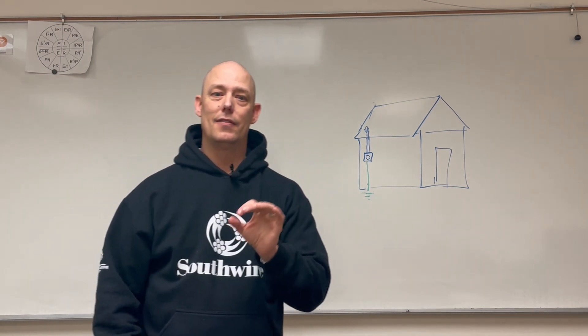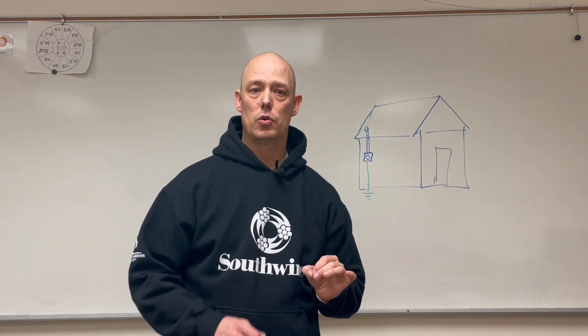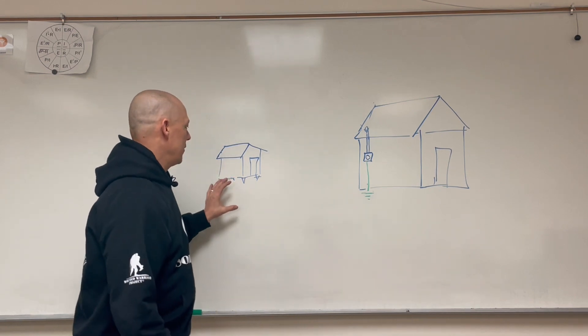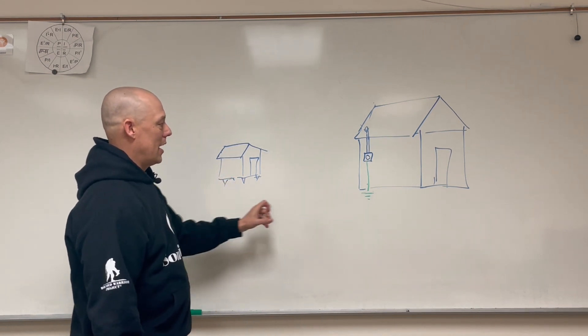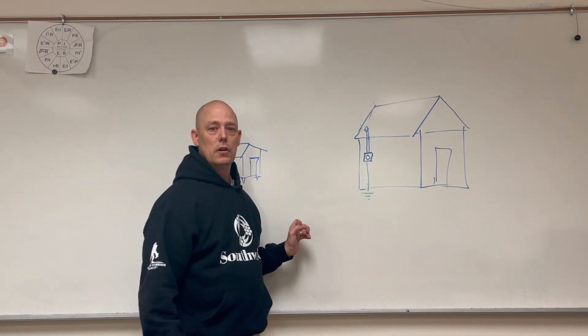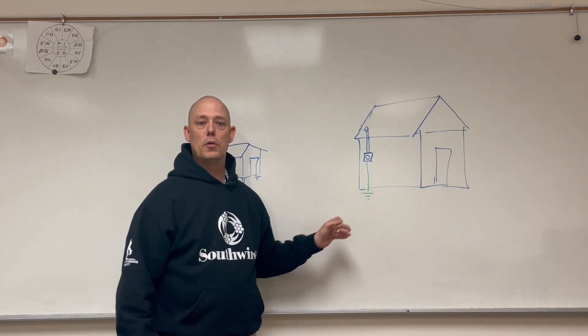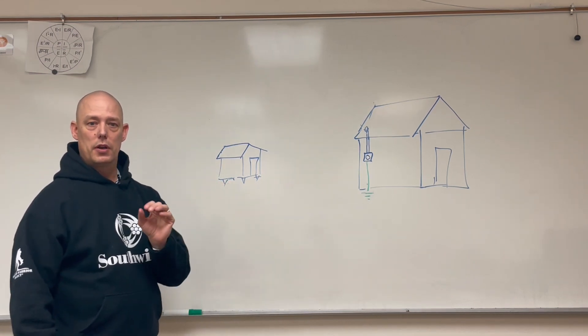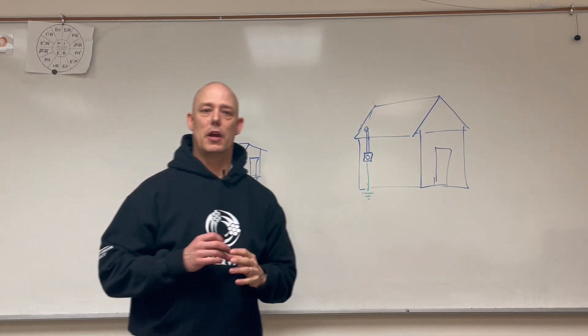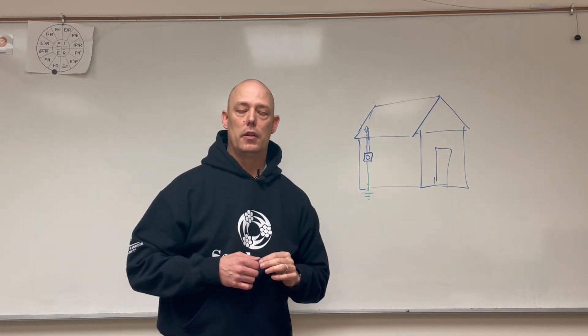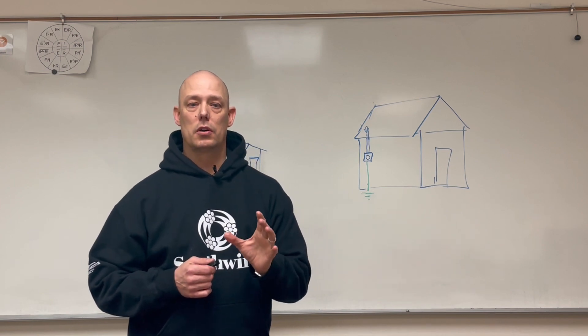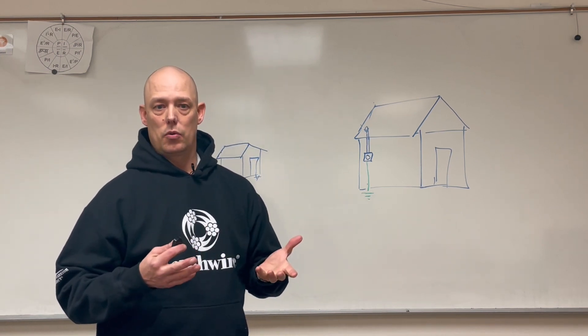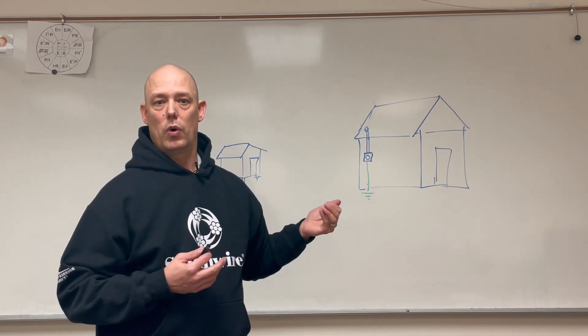You have to go to 225.30. And 225.30 tells us that if we have an accessory building, we can have one feeder or one branch circuit that goes there — we can't have multiple. But it does say at the bottom of that code that a multi-wire branch circuit can be considered one circuit.